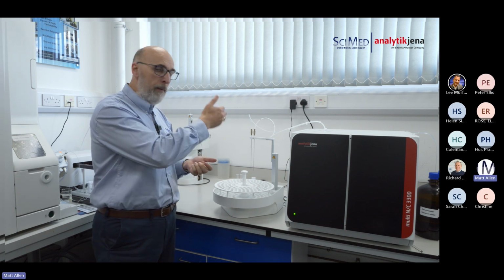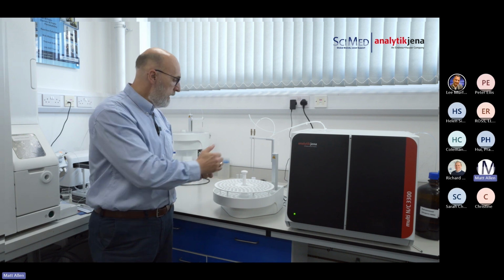It also has some additional features such as external rinse. So if you have particularly sticky or unpleasant matrices, you're rinsing the outside and the inside of the needle. And it has something on this called parallel purging. So if you're doing NPOC, non-purgeable organic carbon, as you are injecting and measuring sample 1, the second needle is sitting in sample 2. It is acidifying that sample and purging off the inorganic carbon before the measurements. But those are the auto sampler options available for the 33 and the 43.